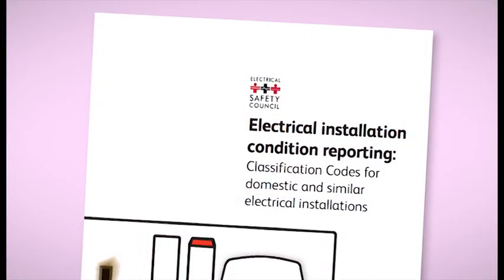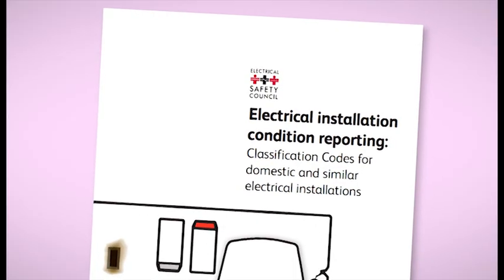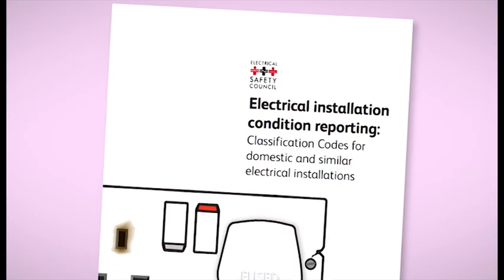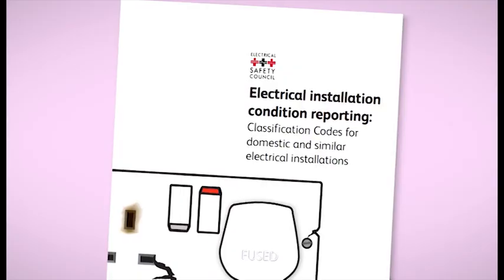Sometimes it will be necessary to indicate that further investigation will be required to decide whether an observation does pose an immediate or potential danger. If this is the case, the overall assessment of the condition of the installation must also be reported as unsatisfactory, as detailed in the Best Practice Guide on Electrical Installation Condition Reports produced by the Electrical Safety Council.